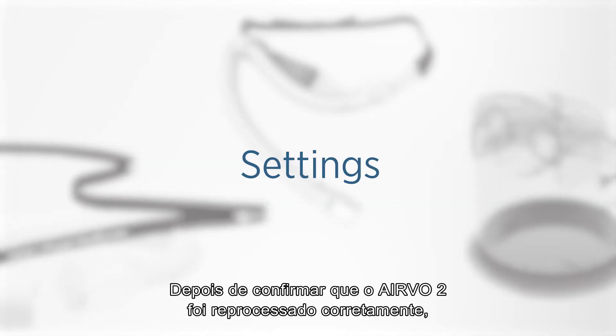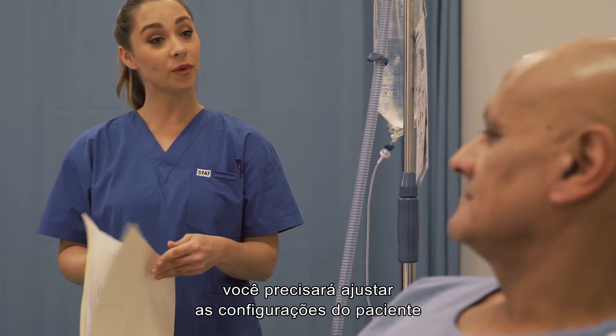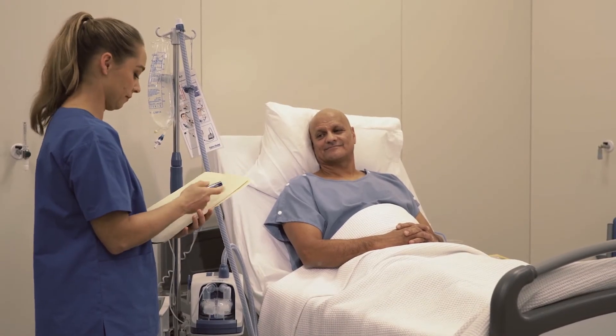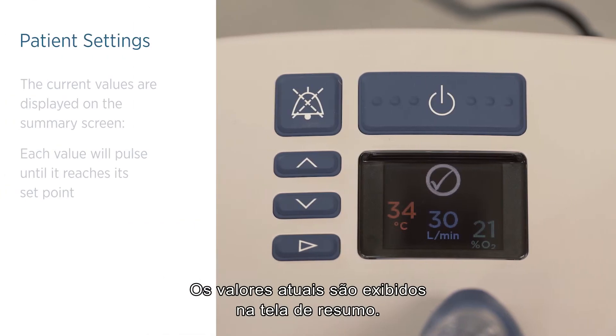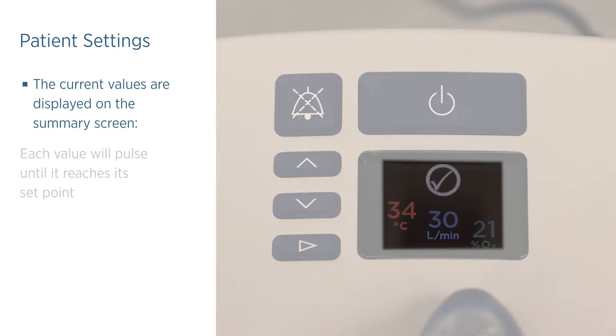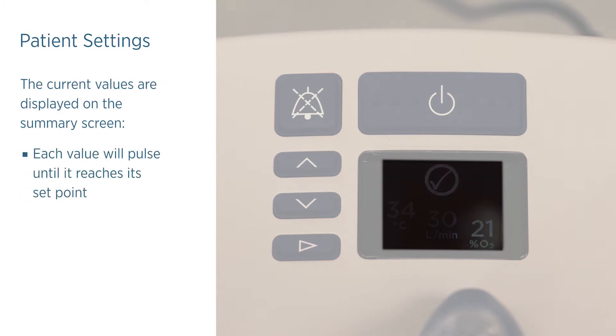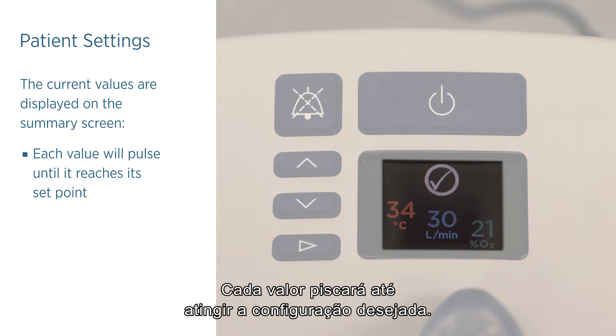After confirming the AIRVO 2 has been correctly reprocessed, you will need to adjust the patient settings to match the treatment required. The current values are displayed on the summary screen: dew point temperature, respiratory gas flow rate, and oxygen concentration. Each value will pulse until reaching its set point.